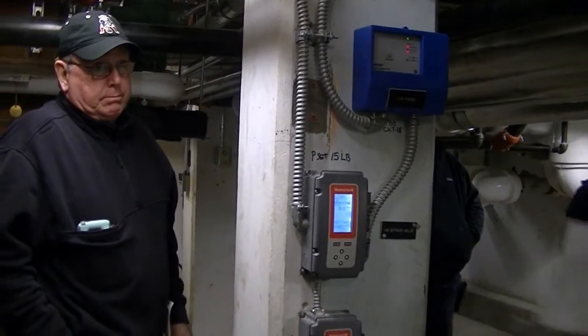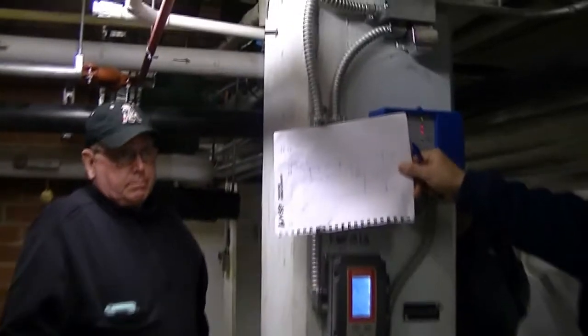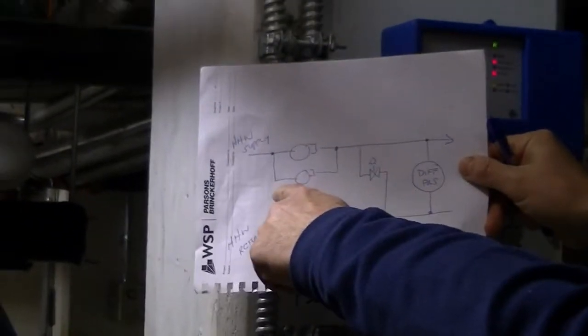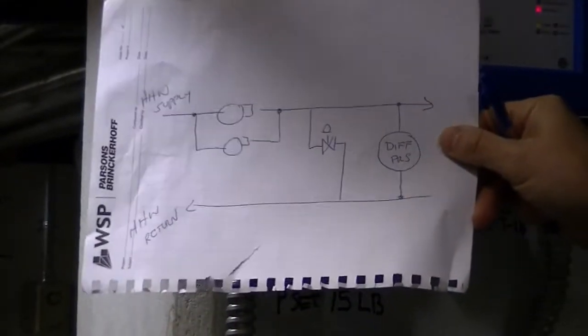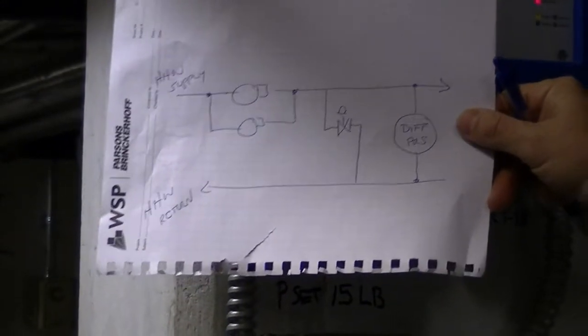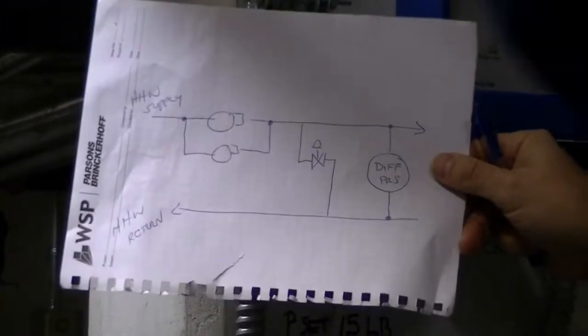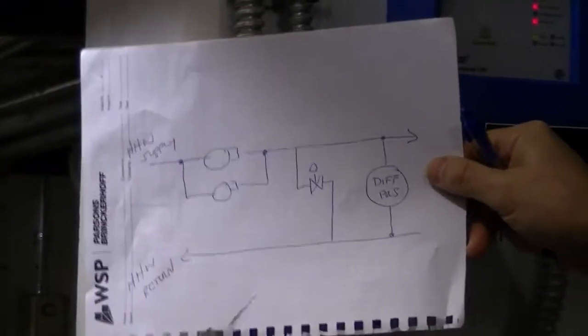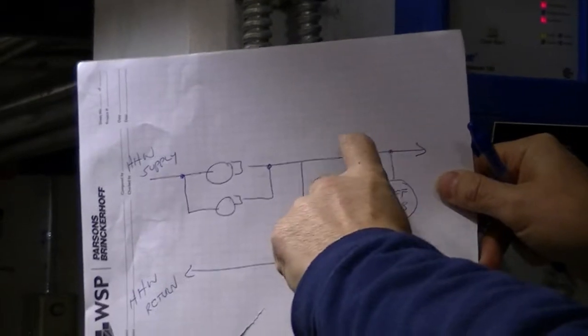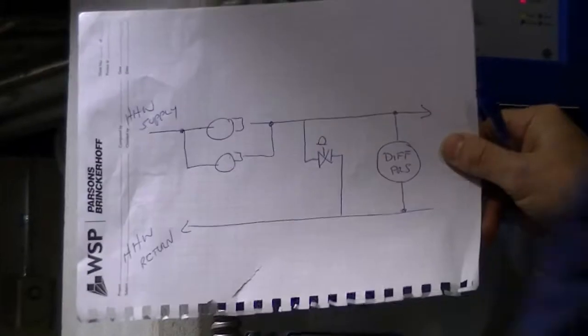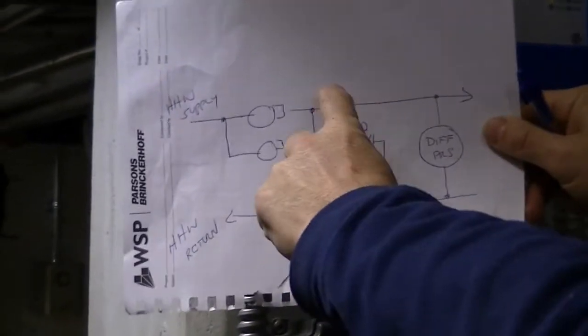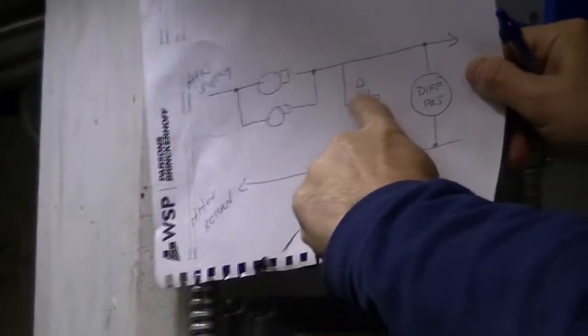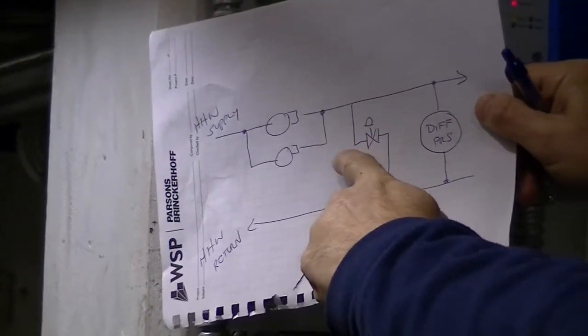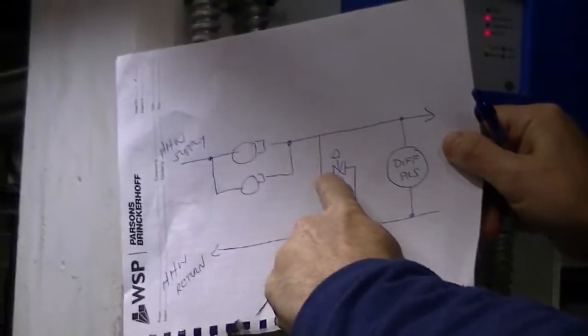Basically with controls here, I'll do it for the camera. Basically, we got the 2 heat and hot water pumps that go out to your buildings. I'm not too sure if this is B&B, if it only serves this side, and ERF serves the other side. I don't know how it's broken up, okay? So you got supply heat and hot water, return heat and hot water coming back through all these buildings, okay? In between that, we have a valve. This is called a differential pressure valve, okay? And I'll explain what that does in a second, okay?